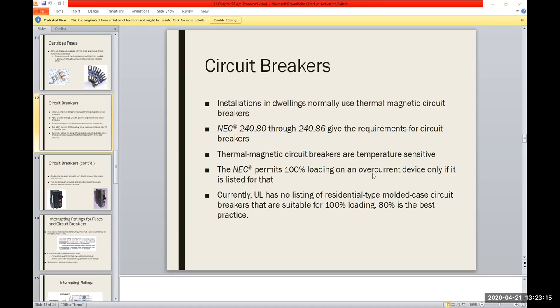And you can look it up in the NEC, Article 240, right? And then you look at the subsections 80 and 86, they'll give you the requirements for what kind of circuit breaker styles you can use. Very typically, it's the thermomagnetics or the temperature sensitive types, right? So if it gets too hot or if the current gets too much for it, it just trips.